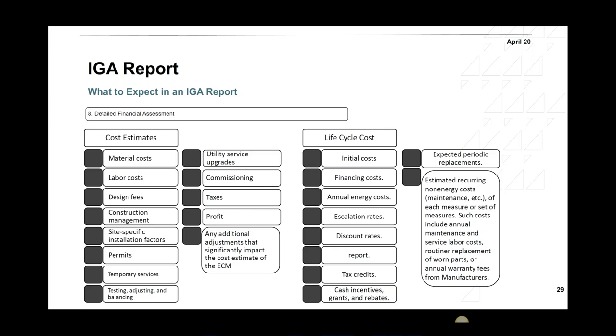Expected periodic replacements for the systems, especially if you're doing a financial model for, let's say, 30 years, and you know after 10 years you might need to change the DX equipment. So you need to put that also in the lifecycle costing. Estimating recurring non-energy costs like maintenance of each measure or set of measures. Such costs will include annual maintenance, service labor costs, replacement of worn parts, or annual manufacturer fees and warranty fees. All these things need to be taken into account. So anything that will cost any penny will be included in the lifecycle cost. This is also from ASHRAE 211.